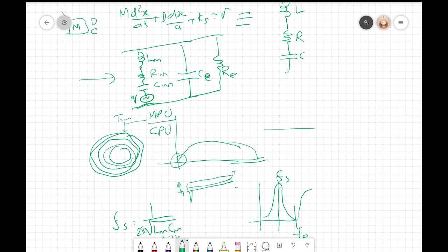So if I make a slender type of transducer, I can twist it. So there are several modes this deformation can take place. So hence, when I talk about this particular resonant frequency, the resonant frequency depends upon the mode in which the crystal displacements take place. So it could be fundamental mode, which is the normal straightforward expansion and contraction. It could be shear mode, it could be twisting mode. Any type of mode is possible.